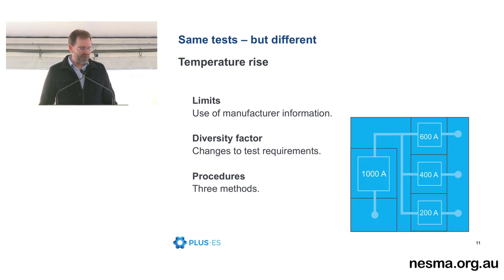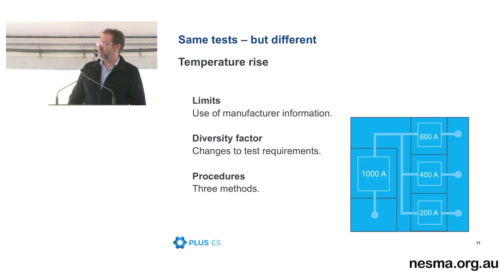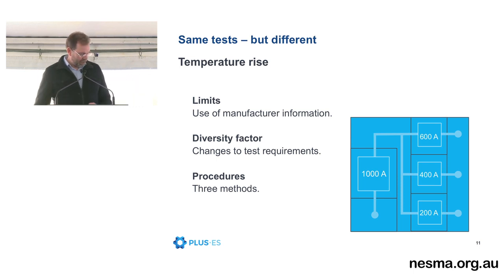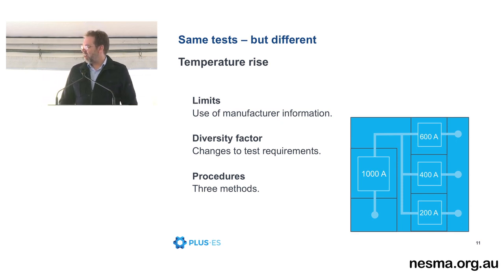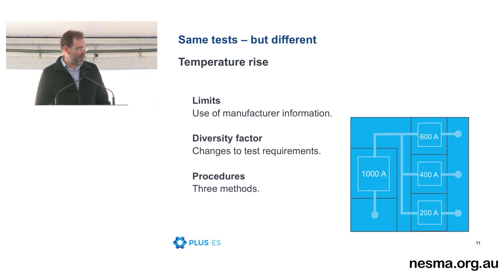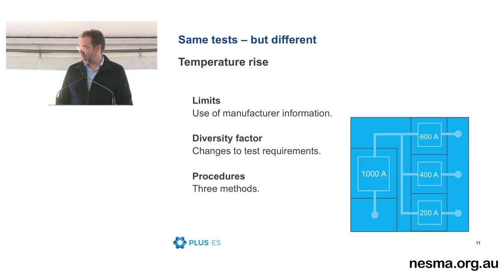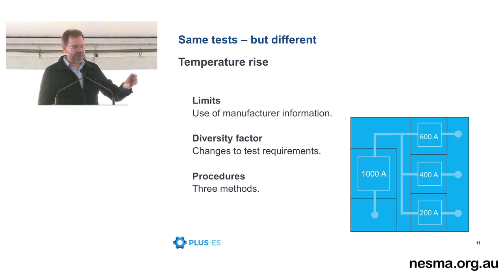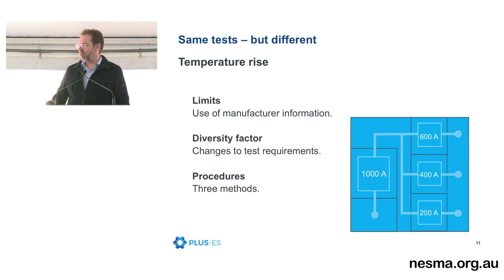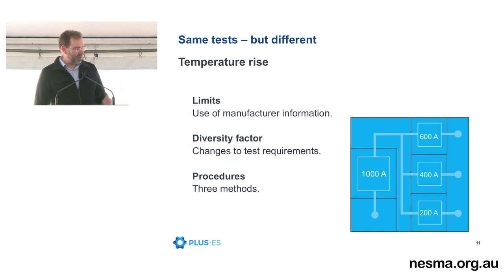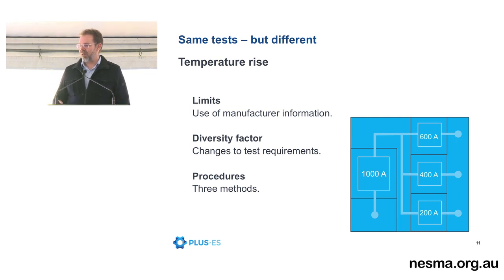All right, so now we've got some same tests but different. So these tests are in 3439, but they're a little bit different. First off, if we talk about the temperature rise, there's a variation on the IEC with regards to the temperature rise table, a table of temperature rise limits, I should say. So you have this big table, and it has all the temperature rise values that different components are allowed to get to. So circuit breaker terminals, external covers, the operating handles.